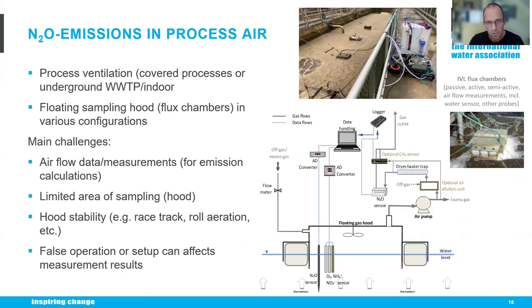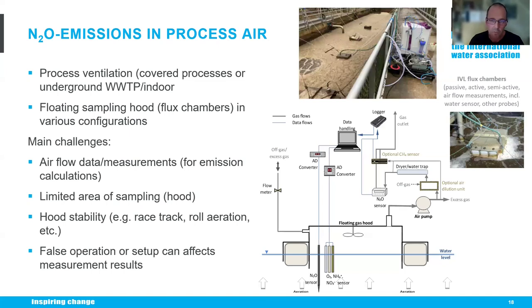For measurement in the process air, if you have a covered process it's quite easy — you can measure in the ventilation. In Sweden many treatment plants are inside bedrock, so you can measure in the ventilation shaft. Otherwise you have to use flux chambers placed on the surface area of different basins. Challenges include: to quantify emissions you need to measure airflow; the flux chamber covers only a small area making upscaling difficult; hood stability may be an issue; and placing the hood at the wrong sites can give quite misleading information about emissions.